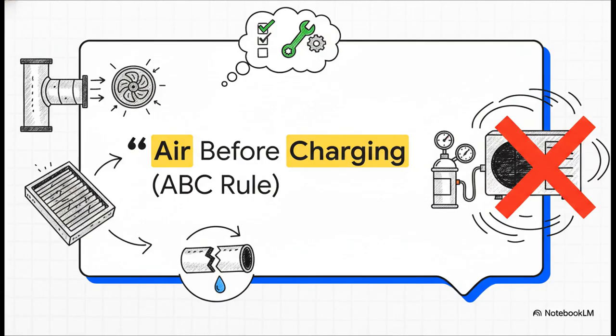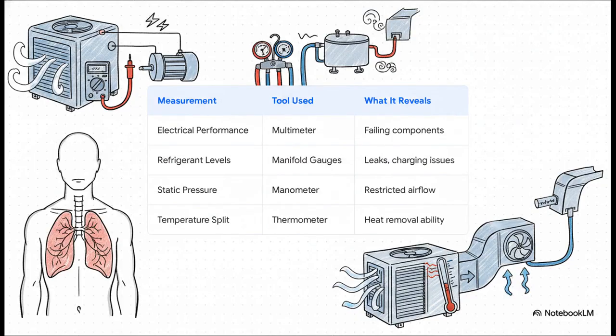This brings us to a really important mantra that the best techs live by: ABC, which stands for air before charging. It just means they will always make sure the system can breathe properly before they ever even think about touching the refrigerant. Why? Because adding more refrigerant to a system that's already choking is just a recipe for a much bigger failure.